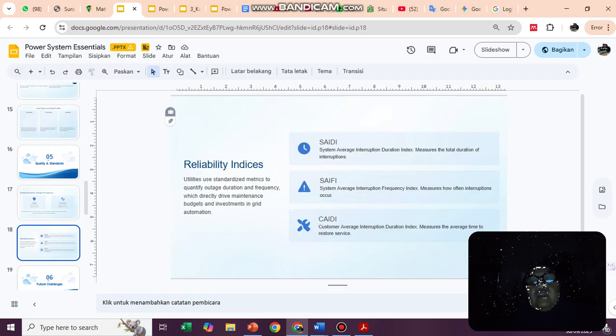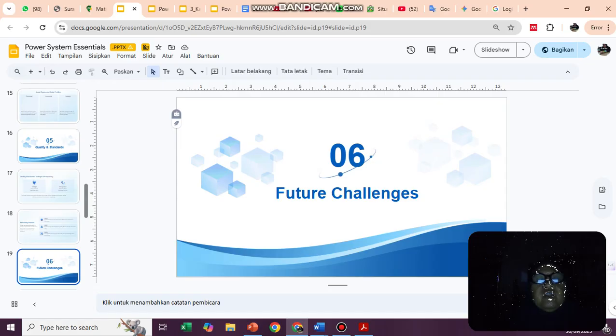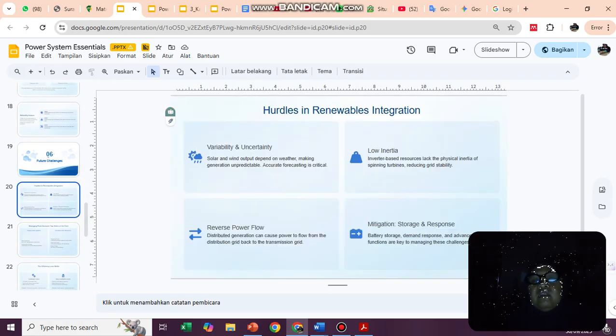And then reliability indices. Utilities use standardized metrics to quantify outage duration and frequency, which directly drive maintenance budget and investment in grid automation. Like SAIDI, System Average Interruption Duration Index, measures the total duration of interruption. And then SAIFI, System Average Interruption Frequency Index, measures how often interruption occurs. CAIDI, Customer Average Interruption Duration Index, measures the average time to restore service.